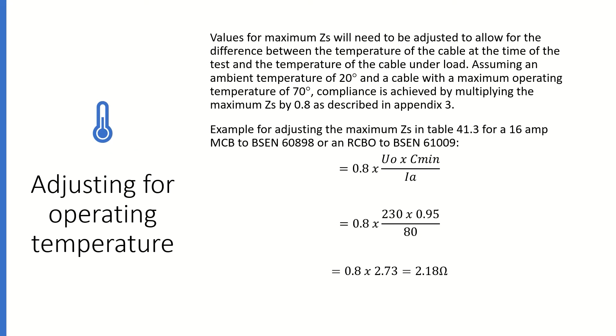So here is an example for adjusting the maximum Zs in table 41.3 for a 16-amp MCB to BS EN 60898 or an RCBO to BS EN 61009. So by multiplying 0.8 by the formula I mentioned earlier, Uo times Cmin divided by Ia, that basically reduces the Zs in table 41 by 20%. So that gives us a figure of 2.18 ohms.